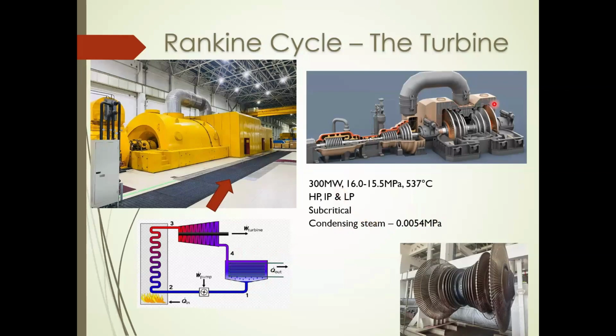So if somehow you manage to overpressure these places, there is something called a rupture disk here, or the diaphragm valve. Now this diaphragm valve is a passive equipment which bursts itself if it detects a high pressure situation. So simply it will burst itself, allowing exhaustion of pressurized steam in the LP turbine or the condenser downstream.